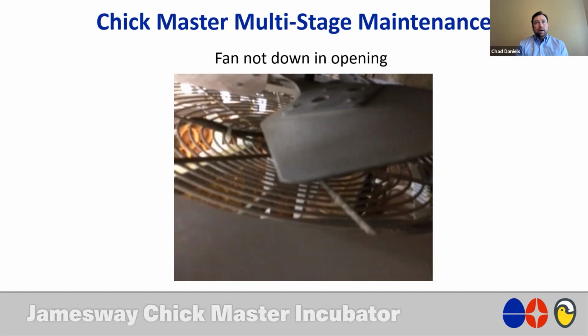And if you do have a fan blade that is damaged or is excessively dirty or is not down in that opening, you will find that one fan that is not moving very much air. That's going to create an odd zone in that machine. It'll oftentimes create overheating or just simply inconsistent temperatures. And as a byproduct of that, it's so easy to pick up on those fans that are completely out of sync simply by feeling for the air.